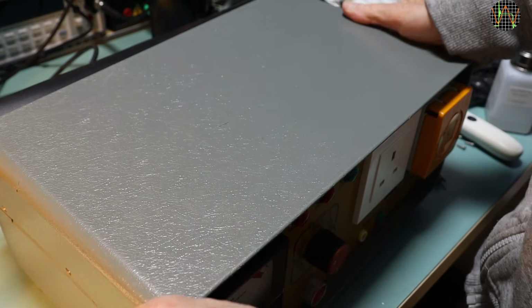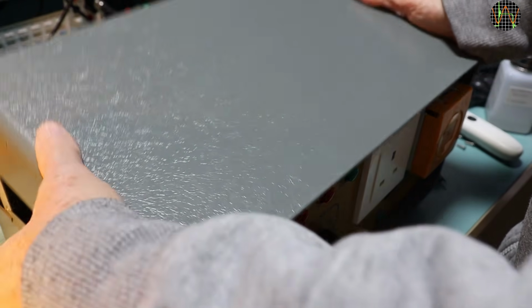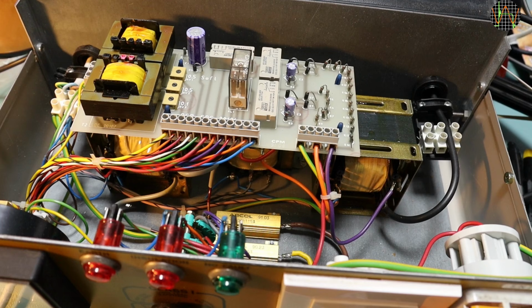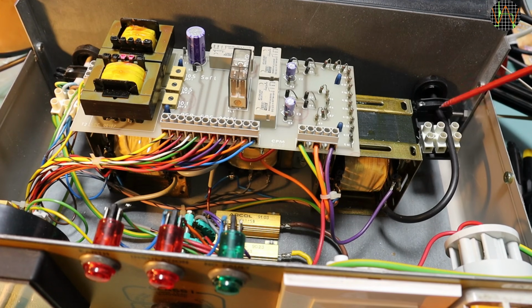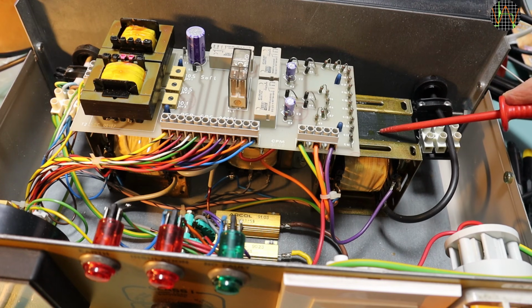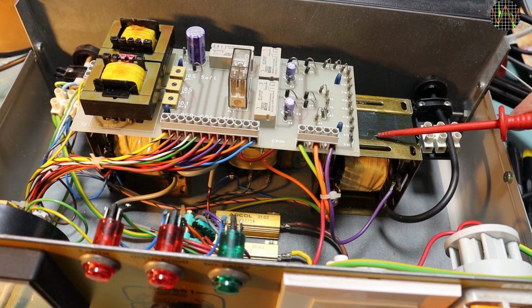After removing 6 screws, the lid, a solid piece of metal, can be lifted off. It looks remarkably clean because there are no vents letting dust in. The inside looks mostly electrical rather than electronic, but there is one PCB. On the far right we have the wire going to the high voltage probe for class 2 devices. This comes directly from the rightmost transformer. This is interesting because it means that the high voltage for class 1 is done elsewhere.